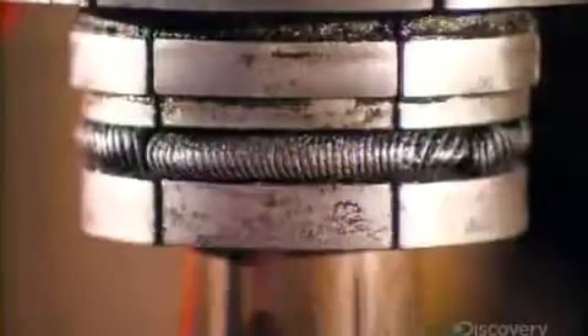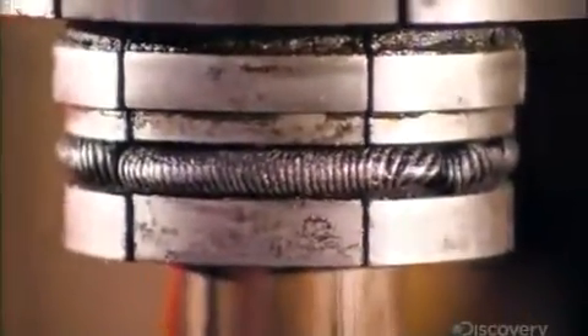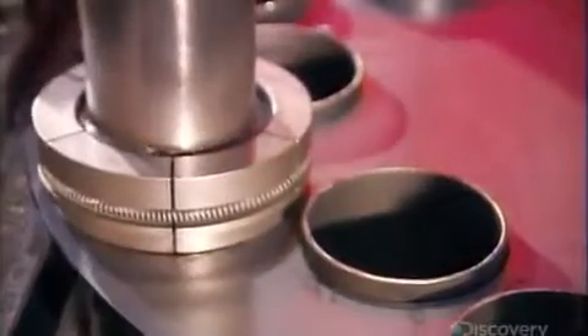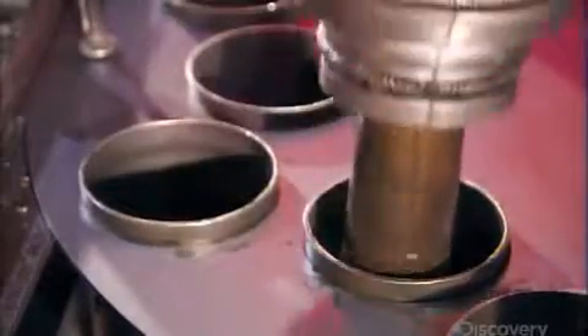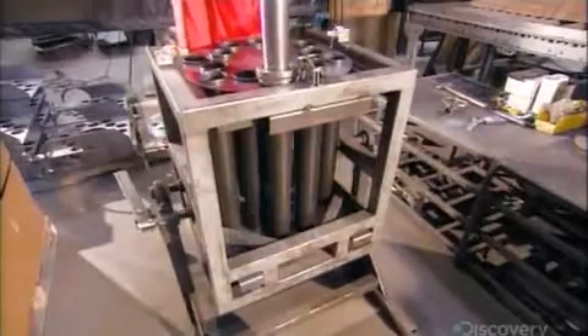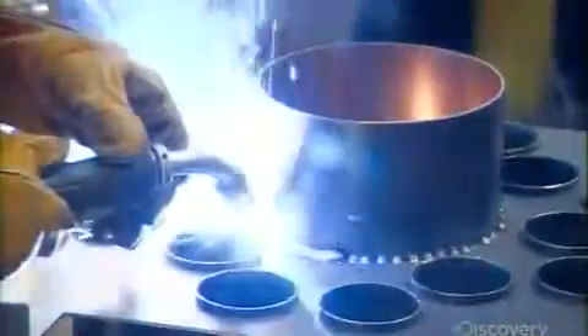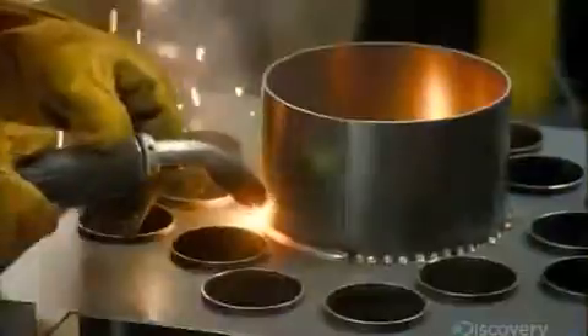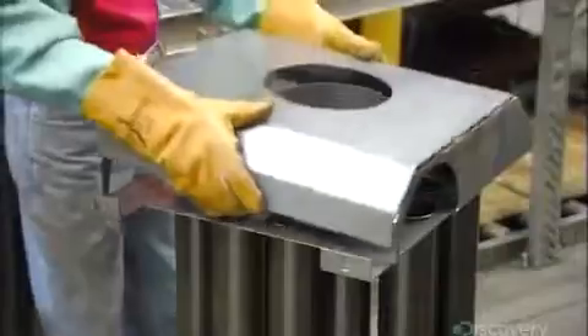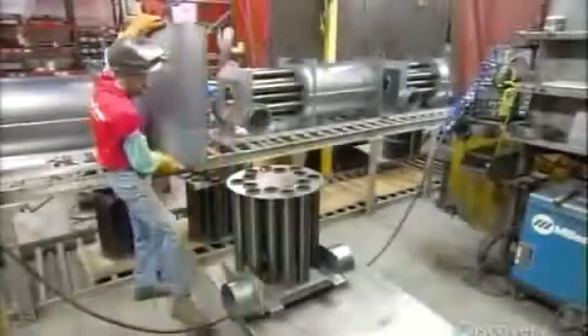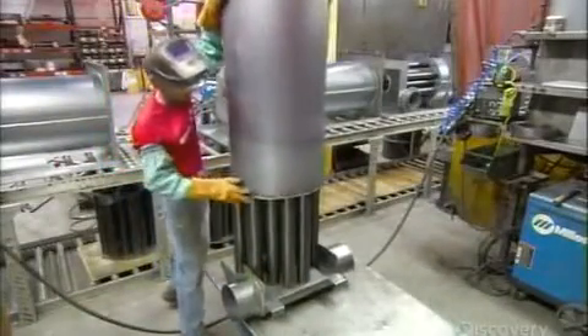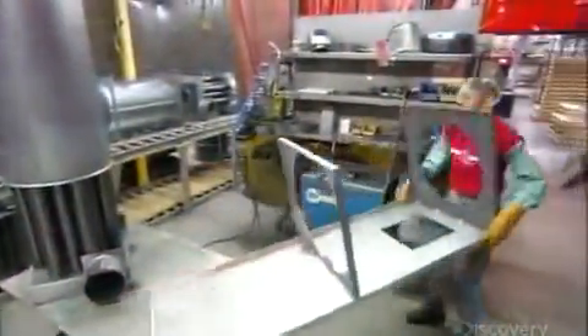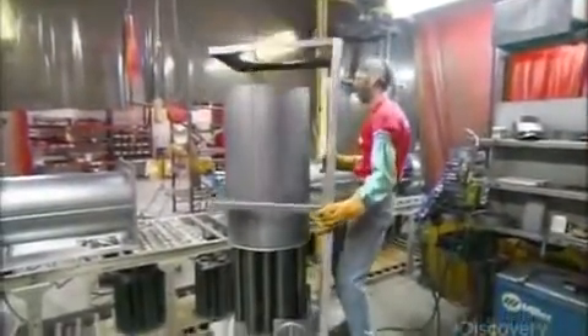This device is called a swaging machine. It expands just the ends of the flue tubes, bonding them in place with the flue plate. Next, he assembles the section in which hot gases collect after passing through the flue tubes on their way out of the furnace. He then sets a combustion chamber on the top of the heat exchanger and welds them together. He completes the heat exchanger assembly by welding on a base equipped with 2 air deflector plates.